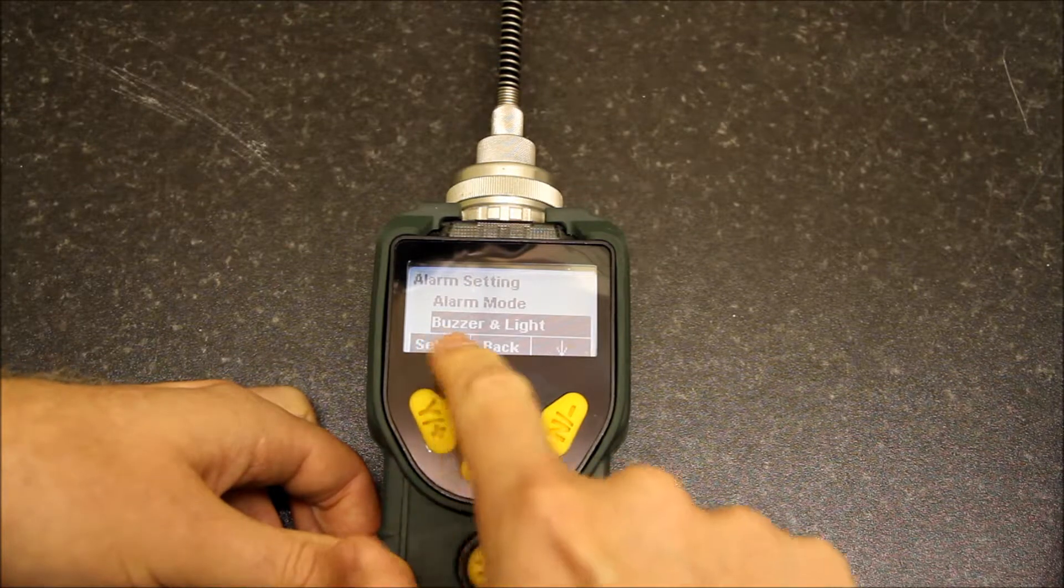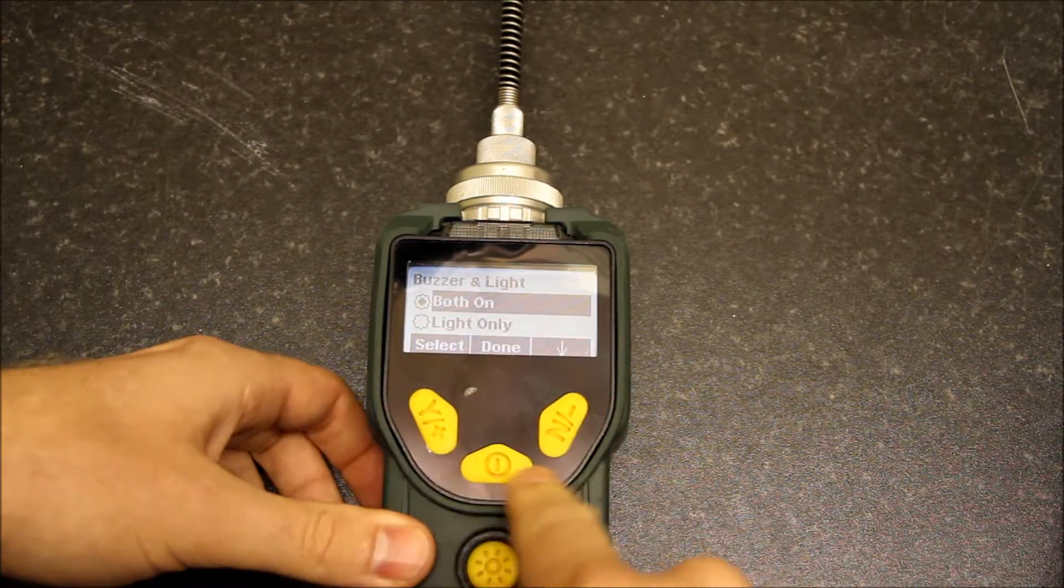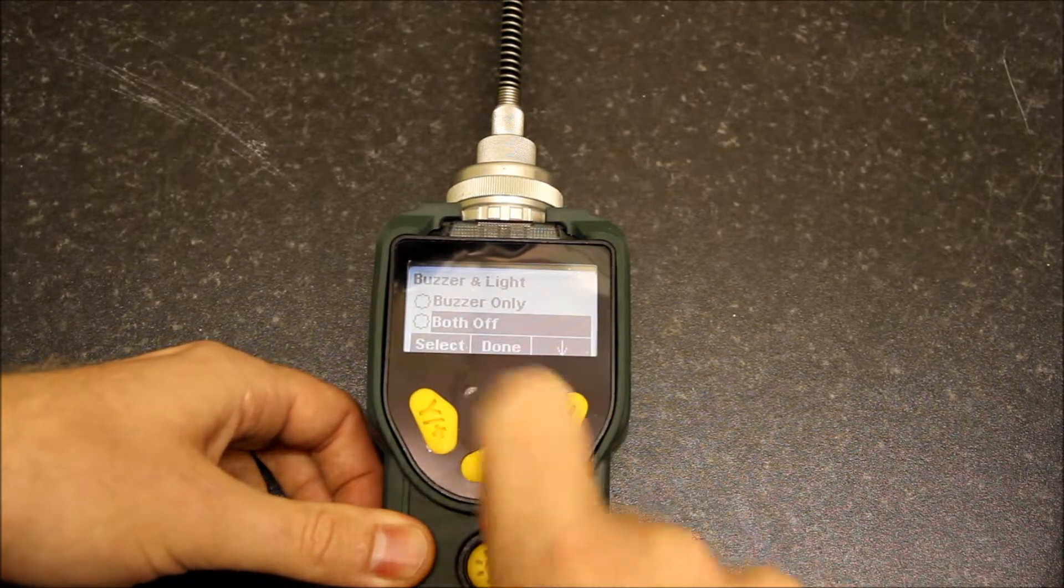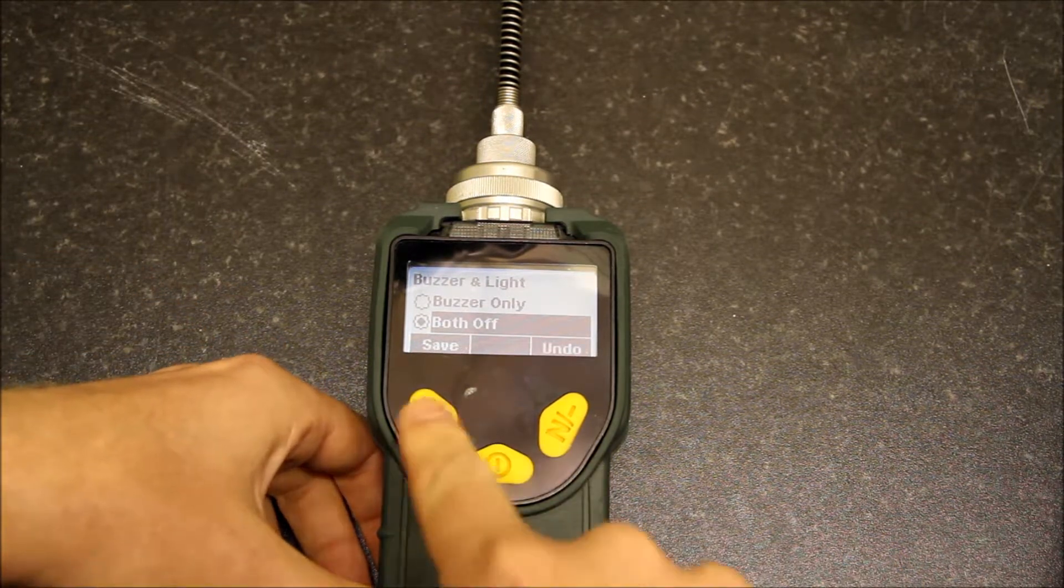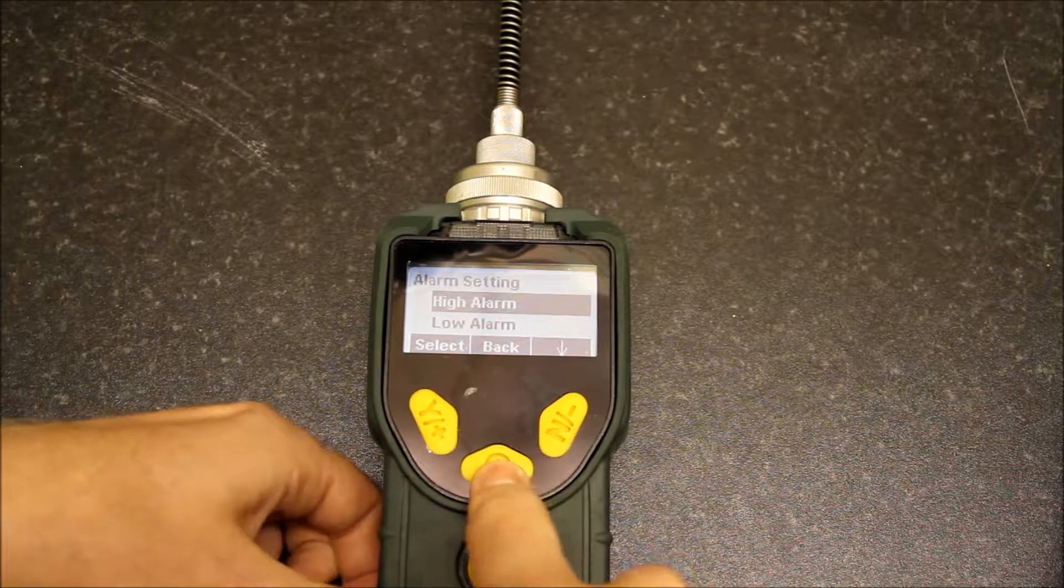Under alarm settings you've also got buzzer and light. If we select this you have both on, light only, buzzer only, or both off. If we put both off and press done to save, the unit will now no longer have any alarms on it whatsoever.